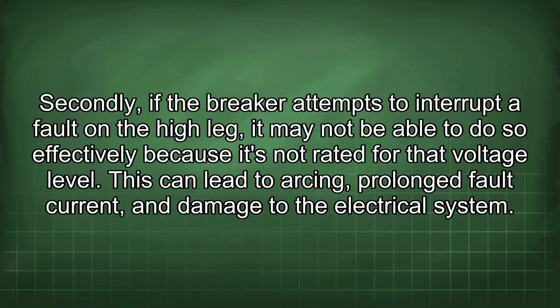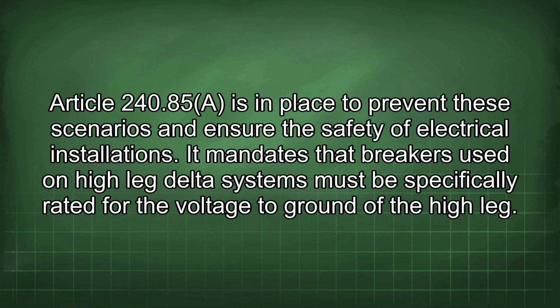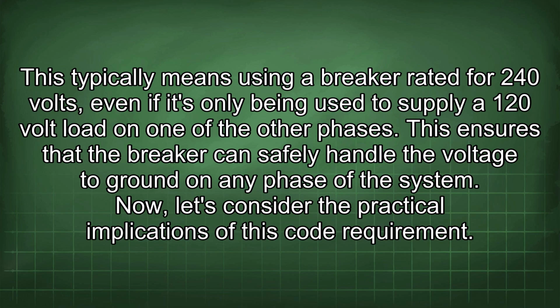Secondly, if the breaker attempts to interrupt a fault in the high leg, it may not be able to do so effectively because it's not rated for that voltage level. This can lead to arcing, prolonged fault current, and damage to the electrical system. Article 240.85 is in place to prevent these scenarios and ensure the safety of electrical installations. It mandates that breakers used on high-leg delta systems must be specifically rated for the voltage to ground of the high leg. This typically means using a breaker rated for 240 volts, even if it's only being used to supply a 120 volt load on one of the other phases. This ensures that the breaker can safely handle the voltage to ground on any phase of the system.